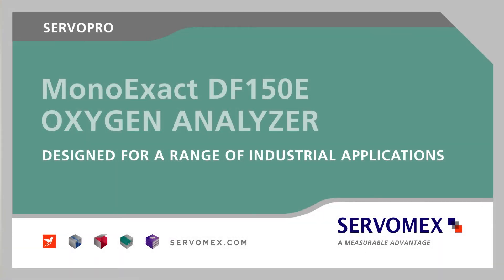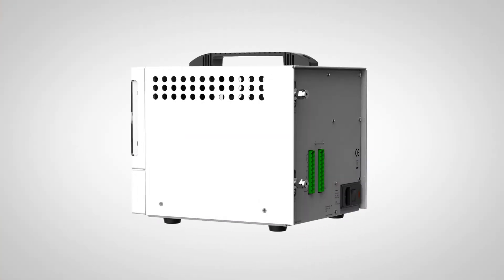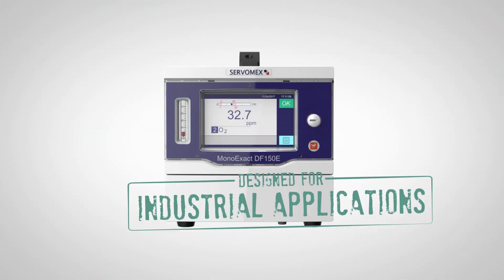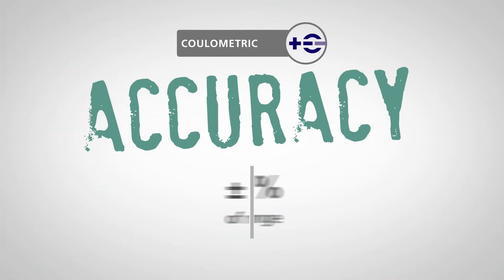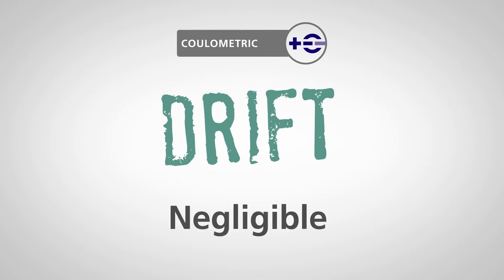From ServoMex, the world leader in gas analysis, the ServoPro MonoExact DF150E Oxygen Analyzer, designed for a range of industrial applications and built around the latest innovations in software and hardware, including a digital coulometric oxygen sensor. It provides stable parts per million measurements with three new ranges from 0 to 10,000 parts per million and three traditional ranges from 0 to 5,000 parts per million, with an accuracy of plus or minus 5% of reading, a full range precision of 0.05%, and limited drift.